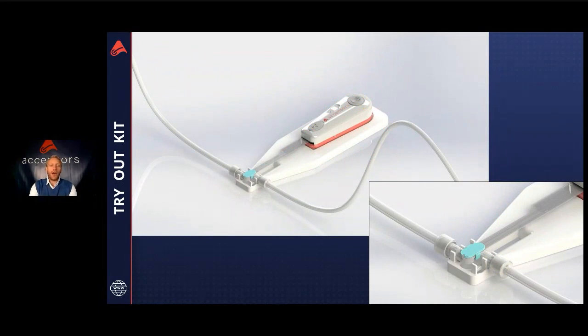And this could be a tryout kit. This is something we have in mind that is not real currently, but it is not a big deal. If you want to measure in a tube system, for example, we could bring our sensor stripe that you saw before, where you can puzzle together the sensor elements you want to have, for example lactate or glucose or troponin or creatinine or sodium, on the stripe, and embed this stripe in a fluid housing with Luer lock adapters, and you can connect it to the tubes. Then you have the possibility to measure these kinds of parameters in a flow system.